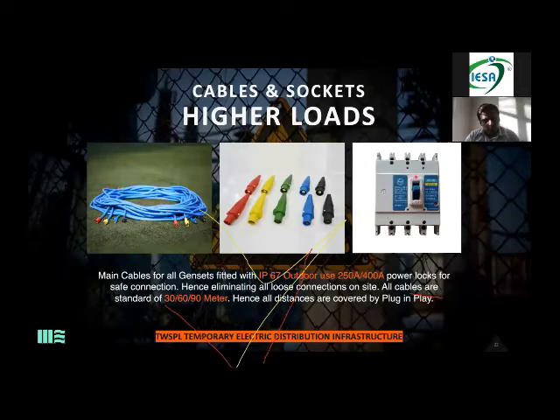We put an MCCB of, maybe if you have asked for 200 kilowatts, we multiply it by 1.7. Maybe you will get around 350 or something odd. And we give him obviously a higher rating MCCB, which is 400 amps. Again, what does it do? It saves you from short circuit, it saves you from overload, and there are certain MCCBs, thermal based, which can also save you from the earth fault. So till the end point where the power is being taken, it becomes an absolutely safe system. So any questions on this?